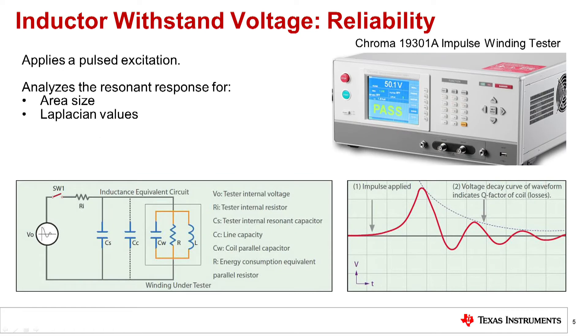Most inductor manufacturers use an impulse winding tester to guarantee each inductor exceeds its specified withstand voltage. The tester applies a pulsed excitation to the device and analyzes the resonant response for area size and Laplacian values.